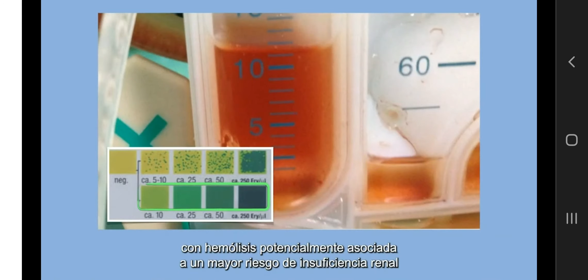Free hemoglobin is nephrotoxic, pro-inflammatory, pro-oxidant, with hemolysis potentially associated with increased risk of renal failure and multi-organ failure. Hemolysis may occur as red blood cells are exposed to excessively negative pressures below 100-120 millimeters of mercury in the setting of drainage failure or too high pump speed, or if red blood cells are exposed to excessively positive pressure above 600 millimeters of mercury, for example due to too high flow or return obstruction.